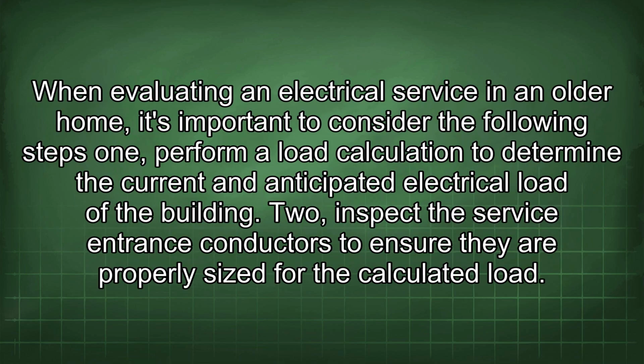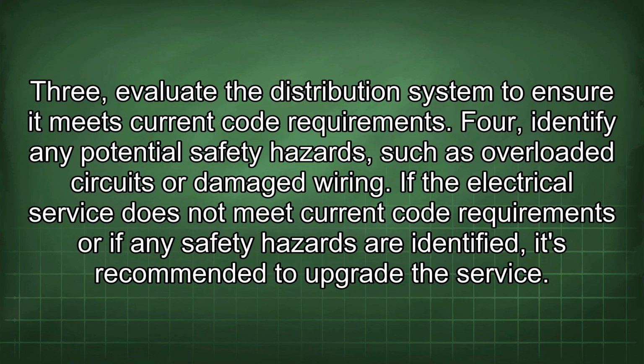When evaluating an electrical service in an older home, it's important to consider the following steps. 1. Perform a load calculation to determine the current and anticipated electrical load of the building. 2. Inspect the service entrance conductors to ensure they are properly sized for the calculated load. 3. Evaluate the distribution system to ensure it meets current code requirements. 4. Identify any potential safety hazards, such as overloaded circuits or damaged wiring.